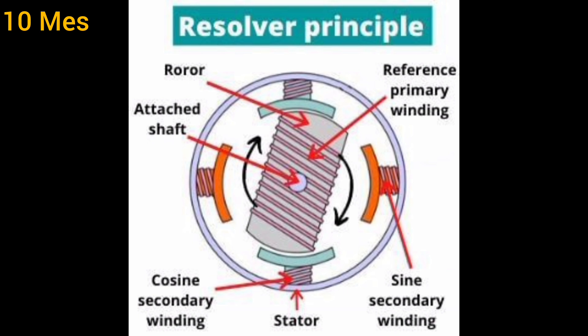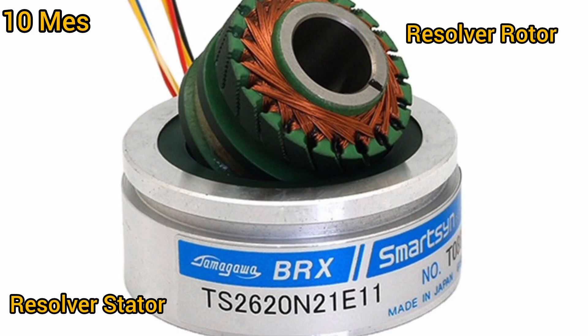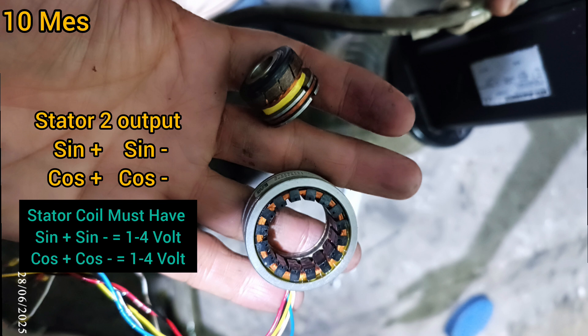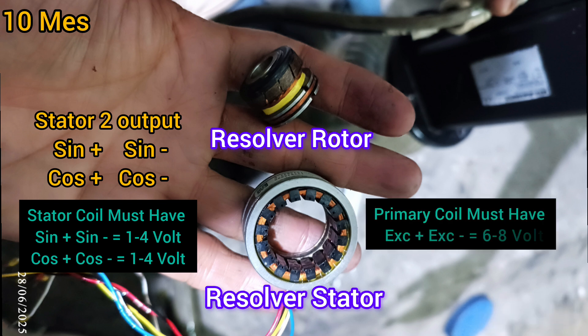Now you can see how to check whether the resolver is okay or not, and what the correct values should be. The stator has a sine coil and cosine coil. The stator sine plus and sine minus must equal 1 to 4 volts, and cos plus and cos minus must equal 1 to 4 volts. The stator has two outputs: sine and cosine.